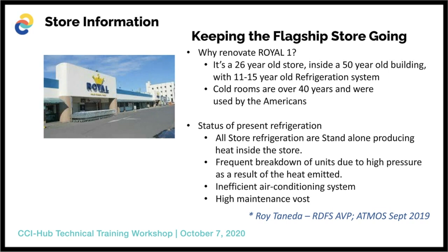The store itself is about 26 years old, as I mentioned, in a 50-year-old building that was operated by the U.S. government. The refrigerated units themselves were approximately 11 to 15 years old. The cold storage facilities themselves are 40 years old, which were continuously run from the time it was still U.S. based. The previous refrigeration system was basically plug-in systems. These things had frequent breakdowns due to high pressure, due to the heat emitted by the plug-in systems. Also, there was insufficient air conditioning to deal with the heat emitted by the systems. And there were also high maintenance costs due to the frequent breakdowns that these systems encountered at the store.